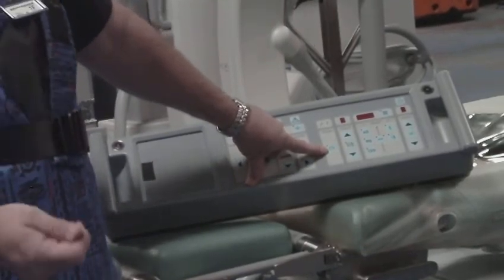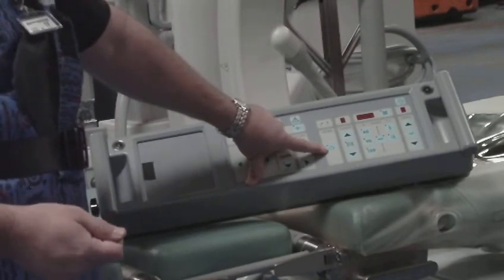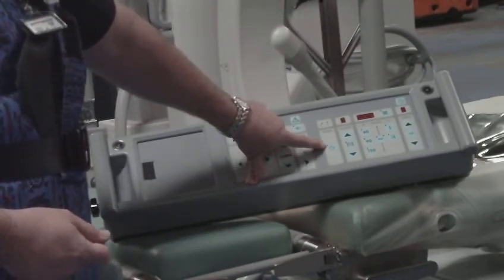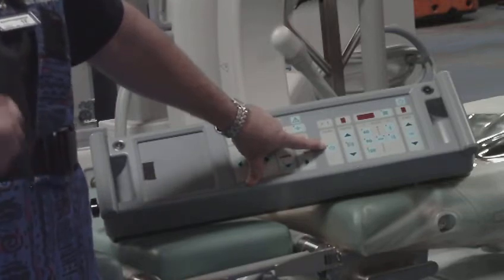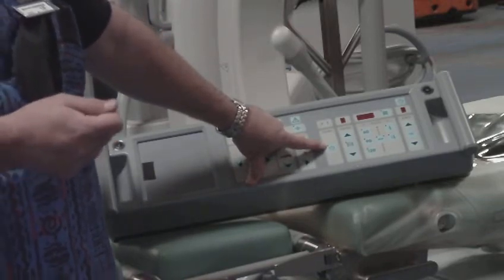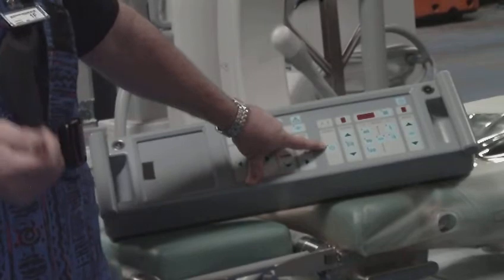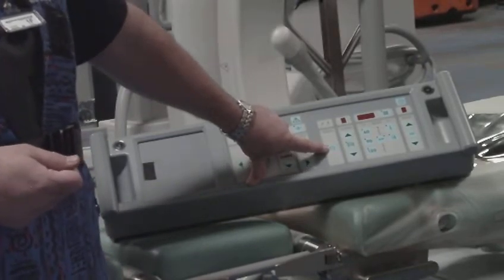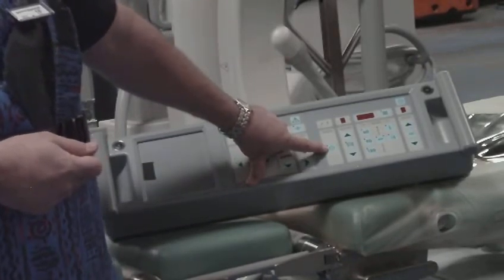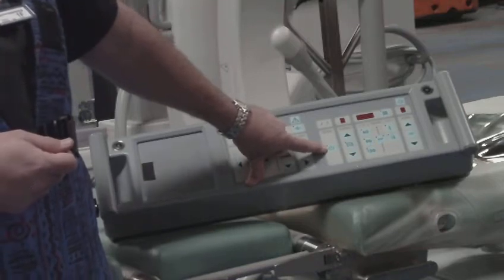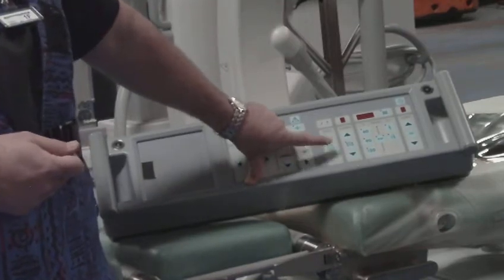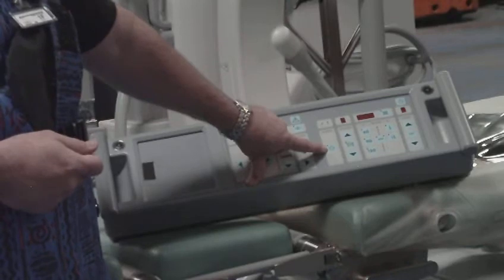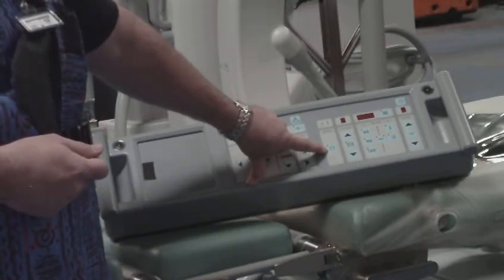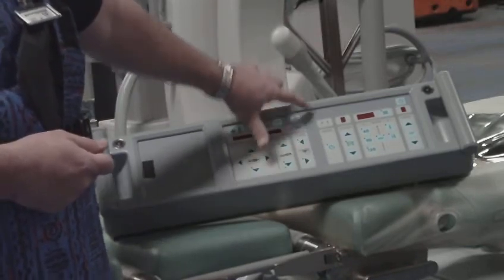So if you want to image while you're scanning, you have to push this button and a little light will come on, and that's telling you that the airbag is up. While you're treating, if you're not imaging, you need to make sure that that's off, because you will lose approximately 50% of your total energy because that airbag's up. So during treatment time is when you need to make sure that it's off.